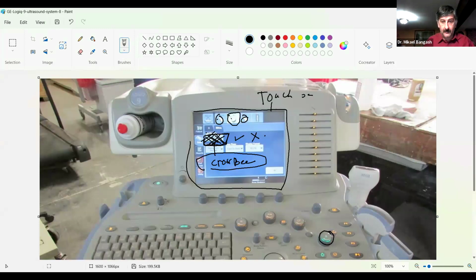This is lit up, so that mainly means that yes, this is the curvilinear transducer, which is this one here, which would have been functioning. But this one is also lit up. So I think that's for this one here. And you have your linear sequential, which most likely will have been this one. So this is how you can choose. You touch on the desired transducer that you want to use, and it's going to turn it on. They're all hooked up. Clear?